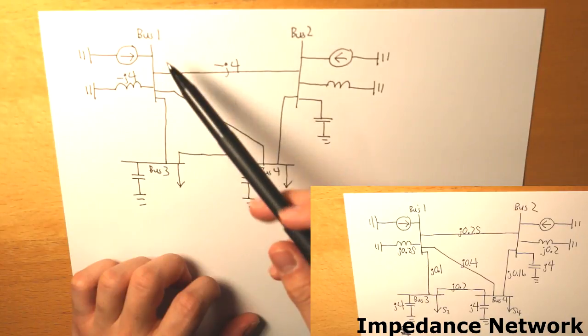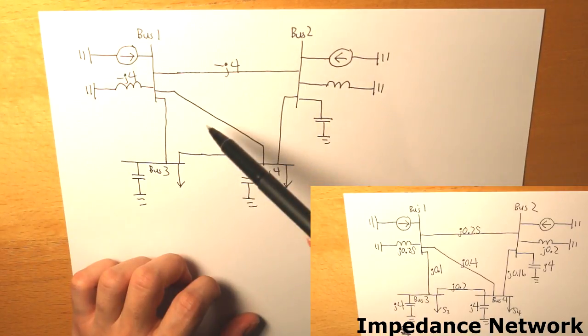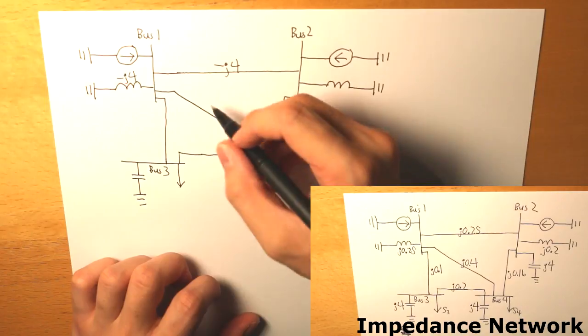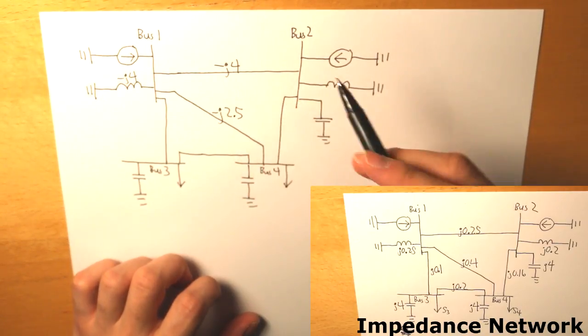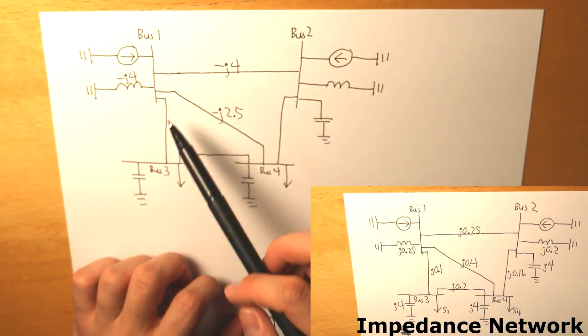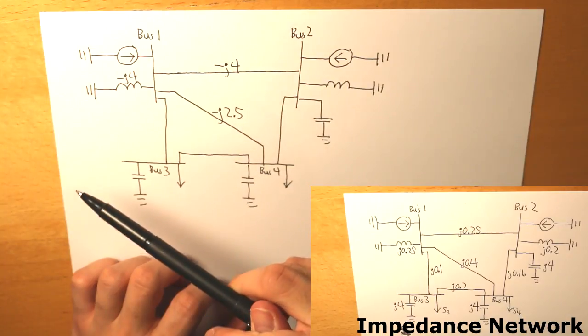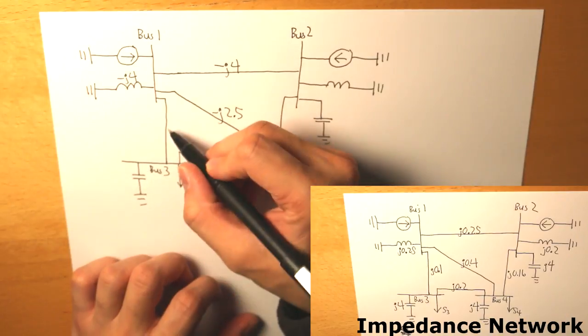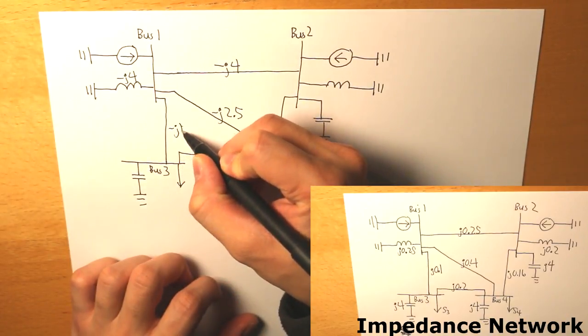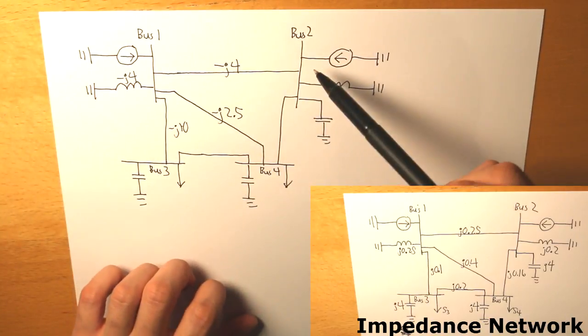For the line from bus 1 to bus 4, the initial impedance value is j0.4, and if we take the inverse of that we get negative j2.5. For bus 1 to bus 3, we take the inverse of j0.1 and we get negative j10.